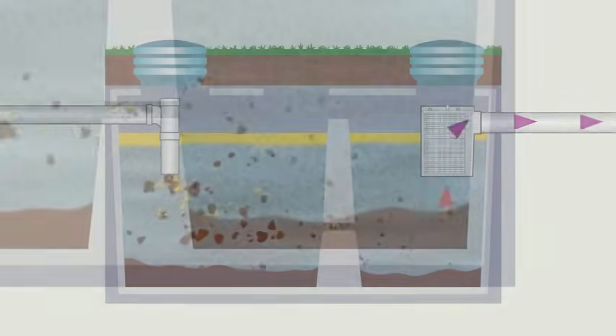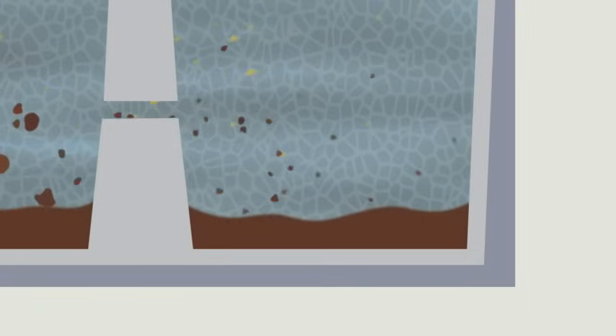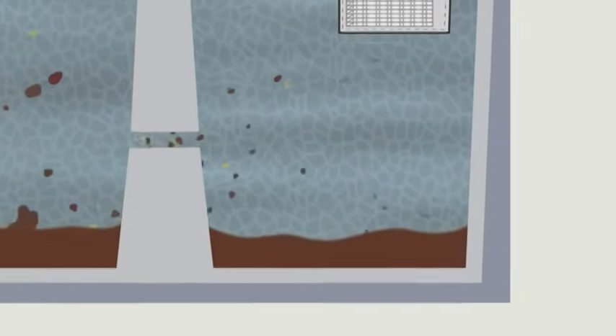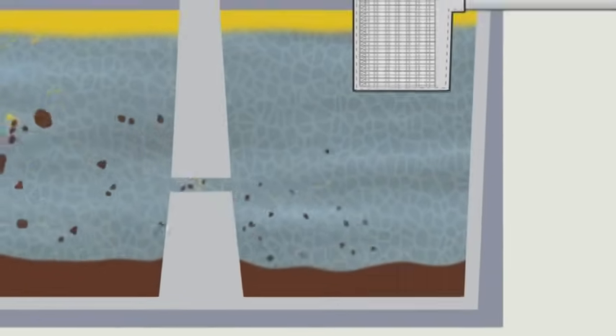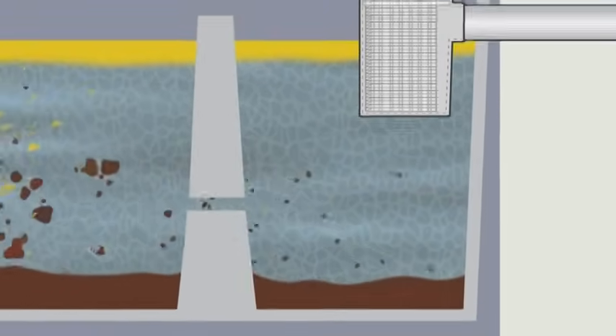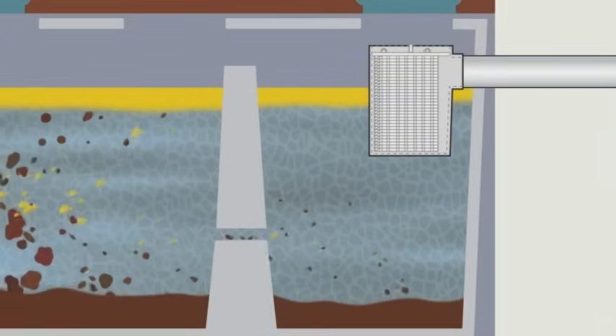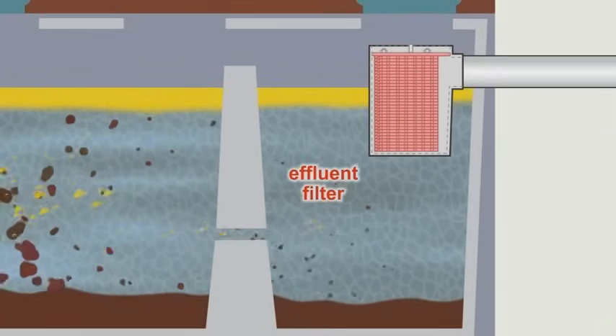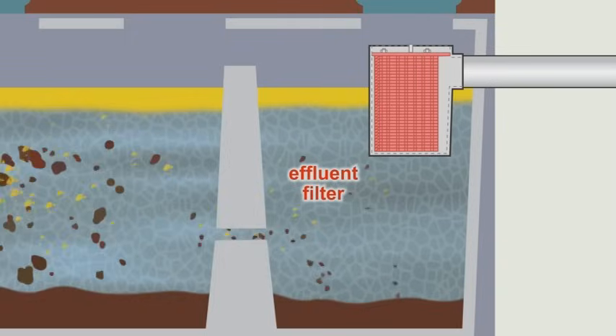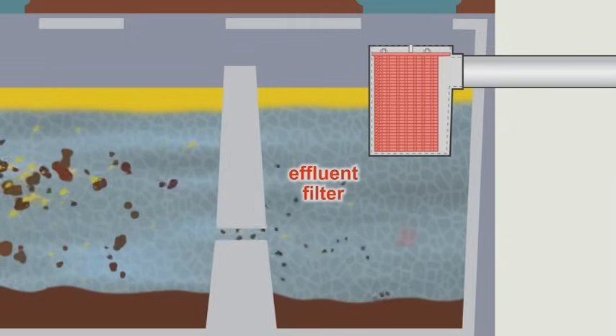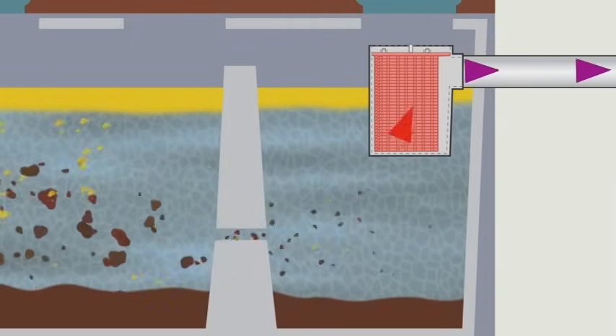A small amount of fine organic particles may settle in the second compartment of the tank, where almost all of what's left breaks down. In systems built or upgraded after 2006, an effluent filter is required to trap and help decompose any remaining particles before they get to the leaching bed.